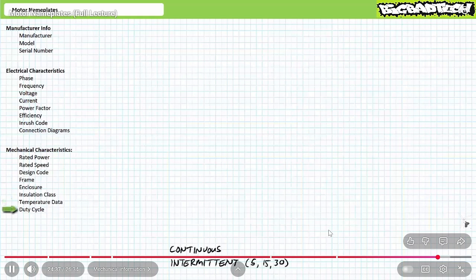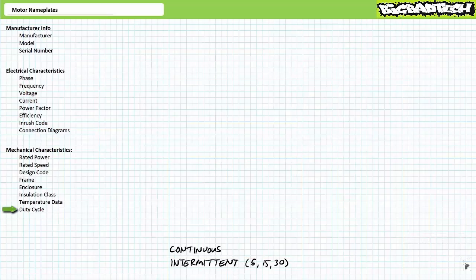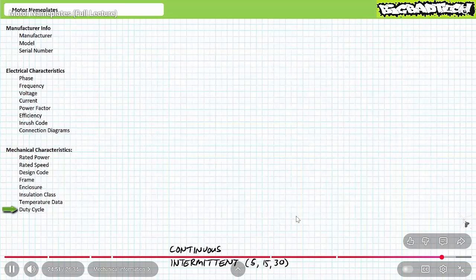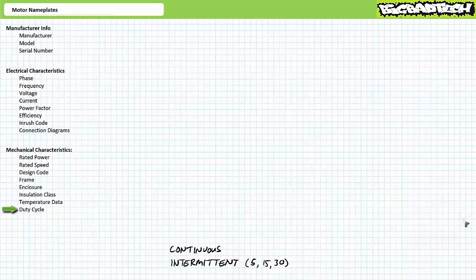Lastly, the duty cycle entry on a motor nameplate refers to the length of time a motor can be expected to run without being turned off and given a chance to cool. If the motor is designed to operate for unlimited periods without rest, it would be specified as having a continuous duty cycle, whereas if it was designed to run only occasionally, followed by a break, it would be specified as having an intermittent duty cycle. Motors intended for intermittent duty will specify the length of time the motor is allowed to run, typically 5, 15, or 30 minutes of every hour.